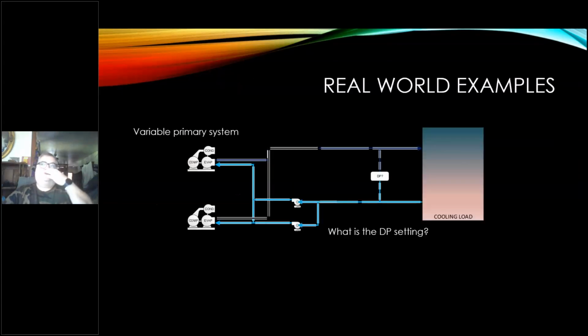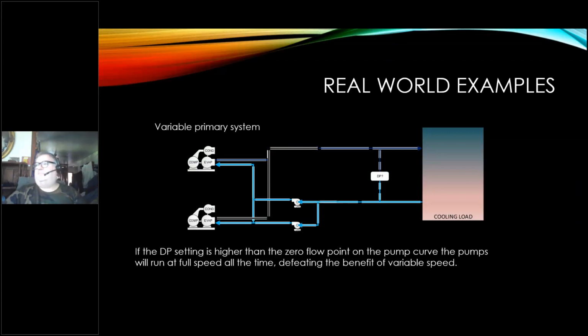So, real world conditions. This is a system that I work on. Very successful, but when I got out there, you may have seen this before. You've got 2 chillers, 2 pumps. Pumps are common together. But you select how many chillers you're going to operate based on the cooling load. And the question I always ask when I look at a system is, what is the DP setting and why is it there? In this case, they had it set up so high that it was above the zero flow point on the pump curve.